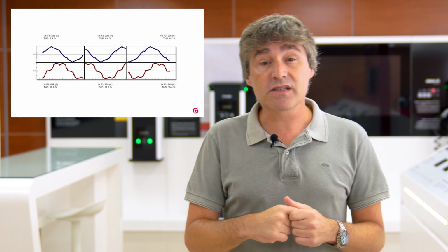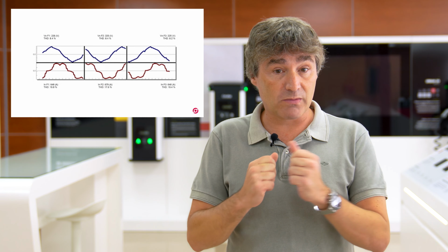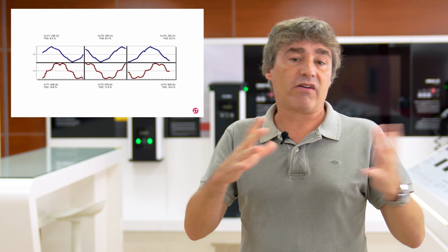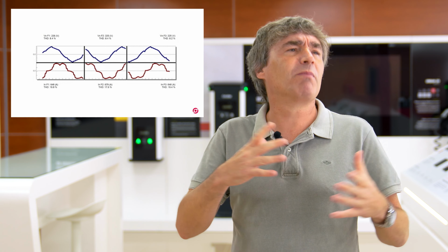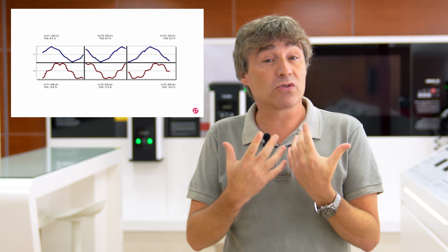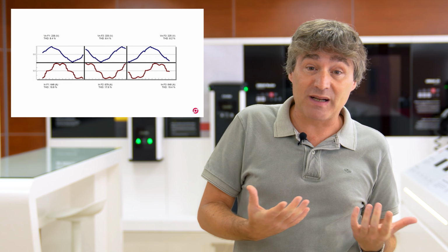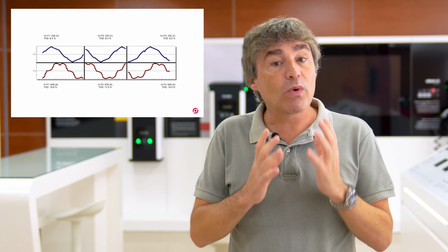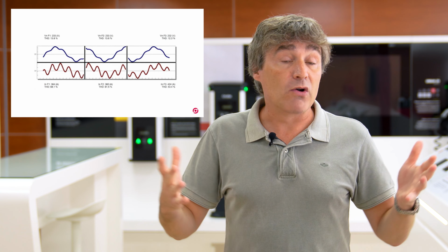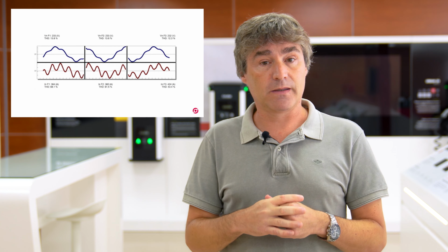Let's look at the voltage and current waveforms when the capacitor bank is off. The total harmonic distortion in current is around 20%, a usual value in many industrial power systems. But in voltage, the total harmonic distortion rates, around 8%, are definitely high. What will happen then if a capacitor bank not equipped with the required component to avoid a resonance event is now connected? It happens what you can see on the screen. Not much explanation is needed, indeed.